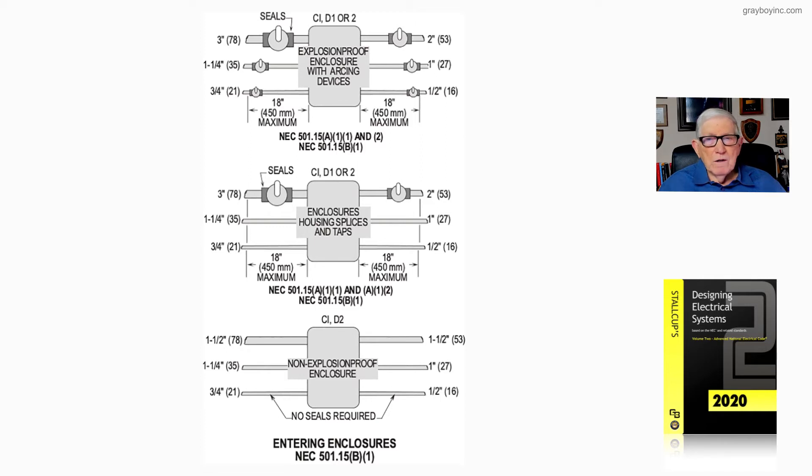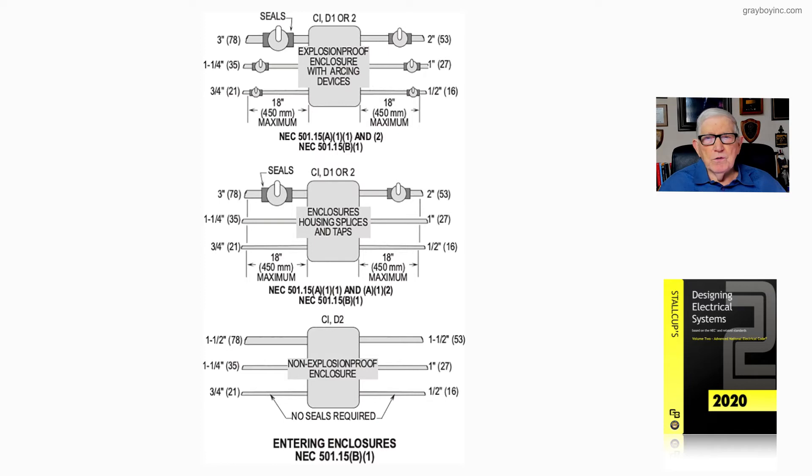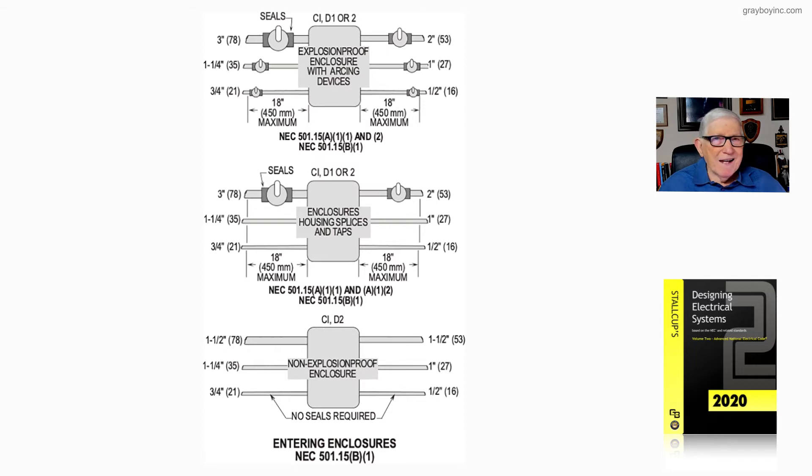That's Class 1 Division 1 or 2. The next illustration shows enclosures housing splices and taps. Notice the conduit has to be 2 inches or larger, then we need a seal.